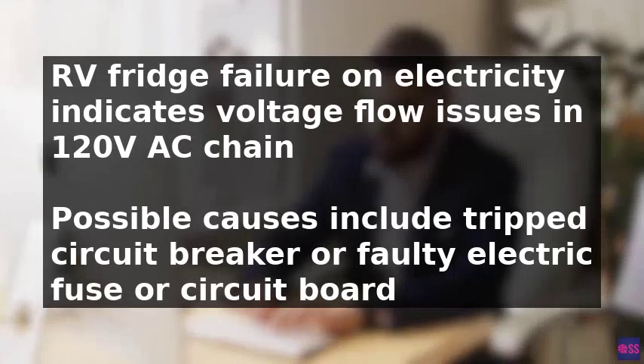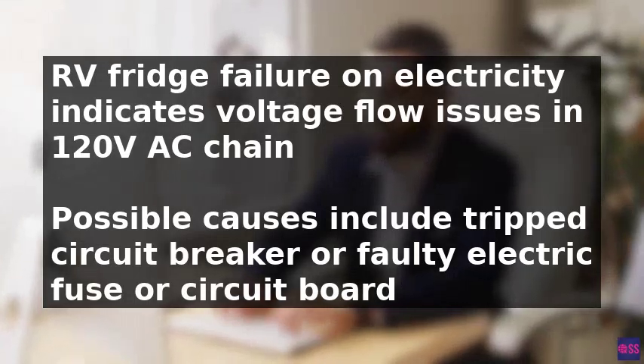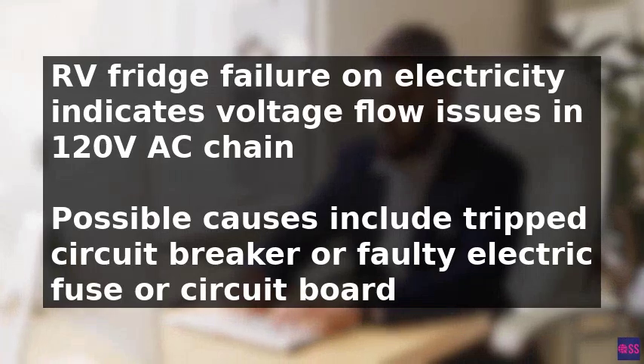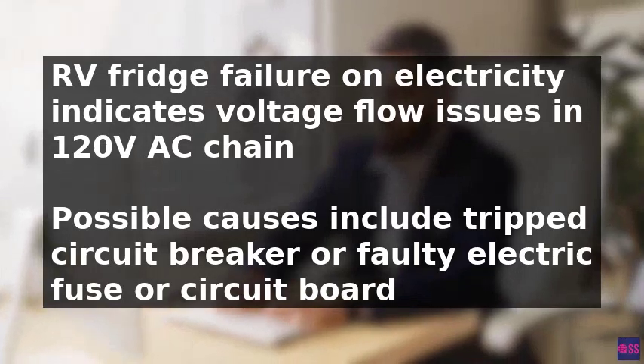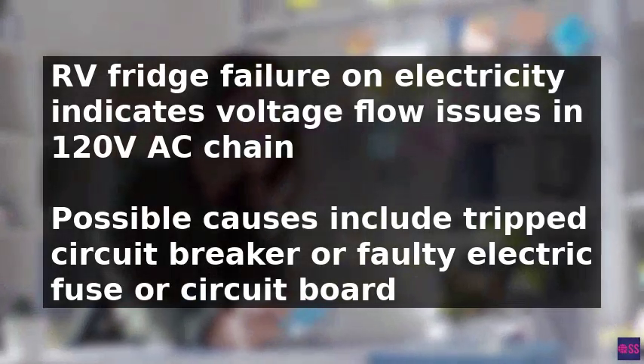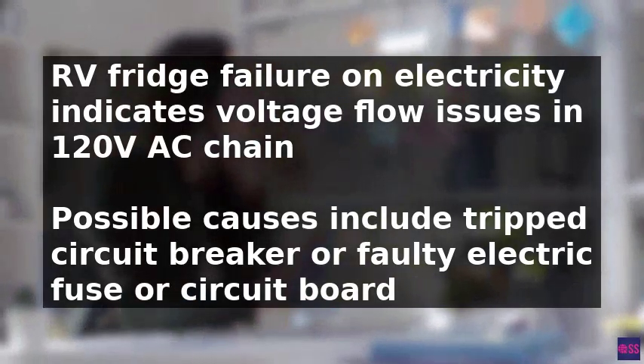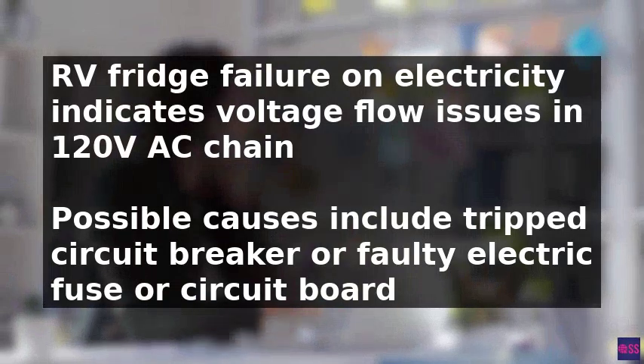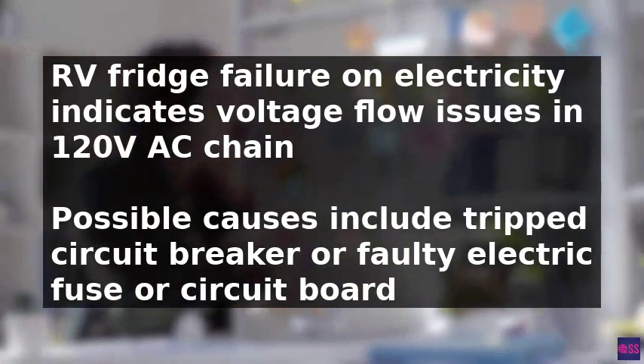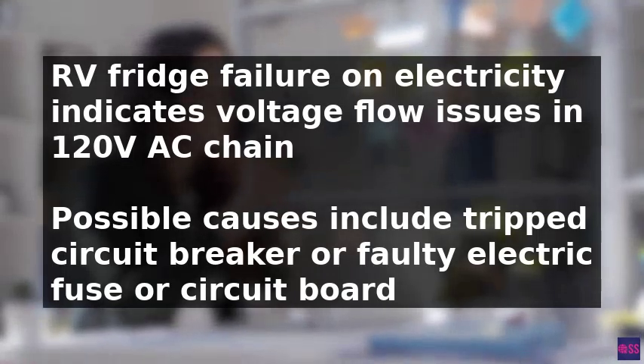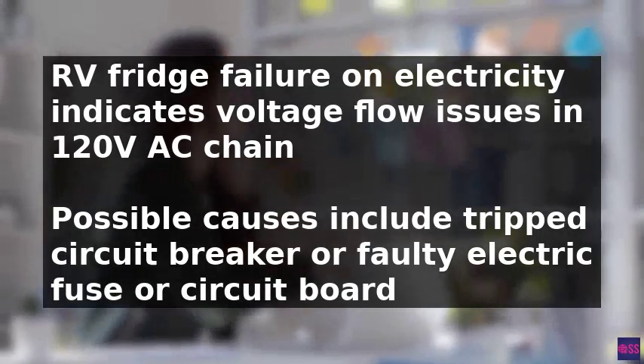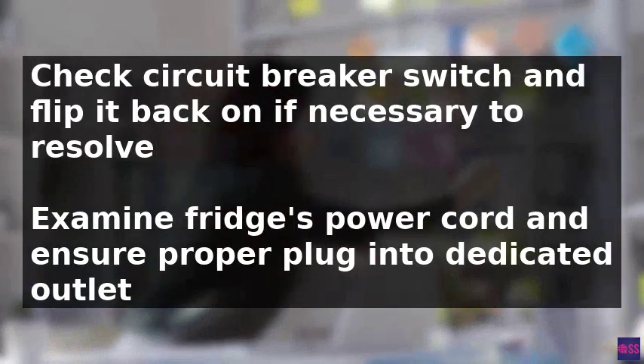When an RV fridge fails to operate on electricity, it typically indicates a problem with voltage flow in the 120 volts AC chain. Possible causes include a tripped circuit breaker in the electrical panel box, an unplugged power cord, a faulty 120 volts electric fuse, or a defective circuit board.